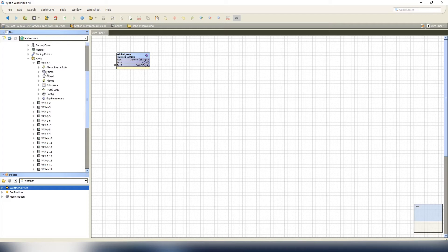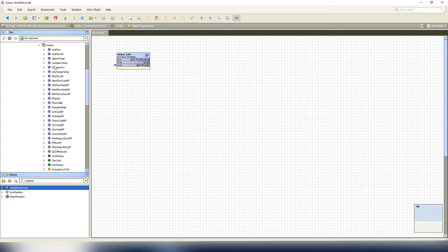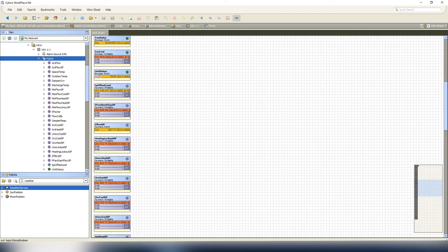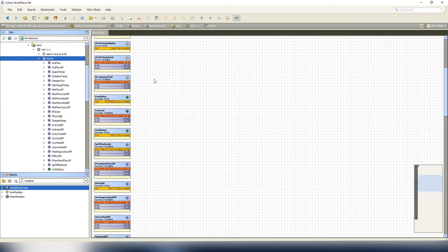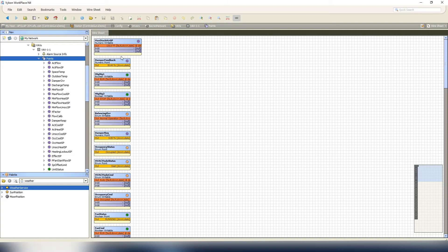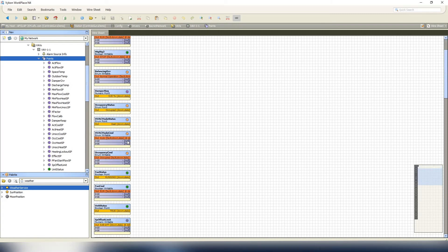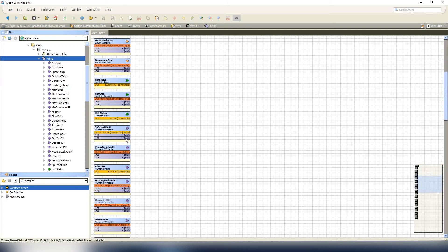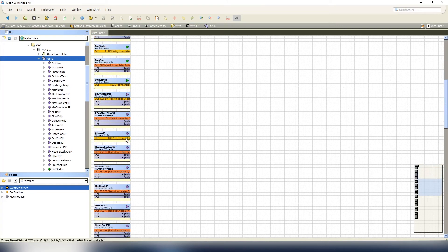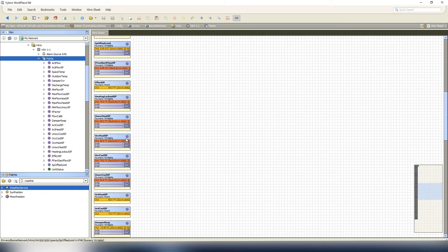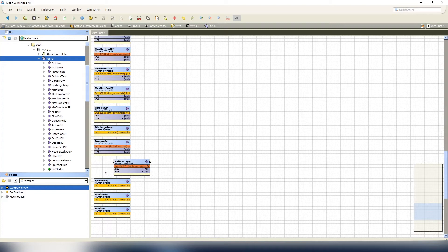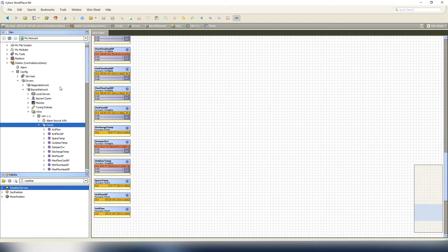Just to make it a little bit easier, as I expand our points, you can see we have our outdoor temp here. I will show you guys the wire sheet to prove that nothing is linked. I apologize, I just copied and pasted this, so it may have a value, but it'll show you that nothing is linked. Outdoor temp right here - as you can see, no link marks at all to any of these points.